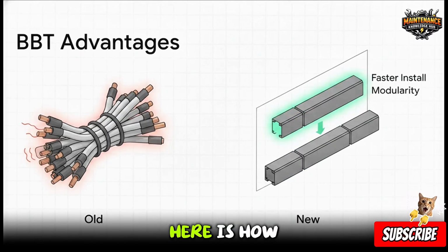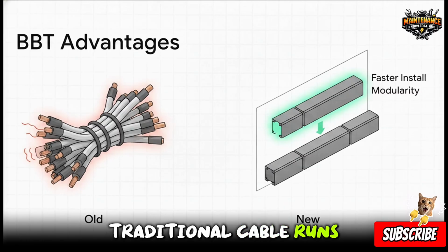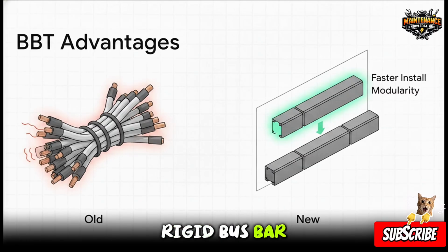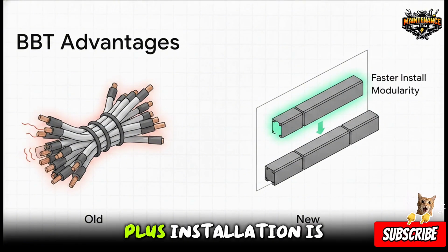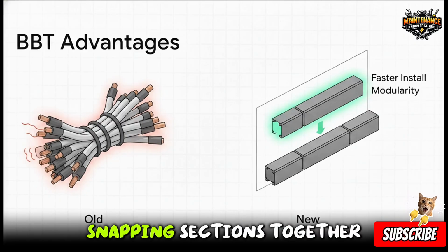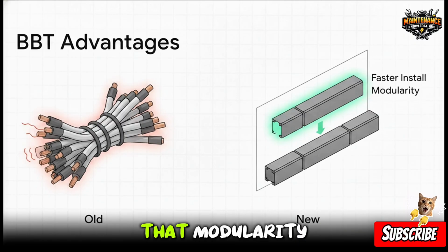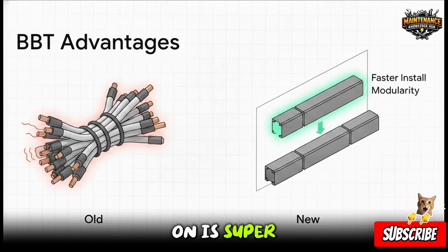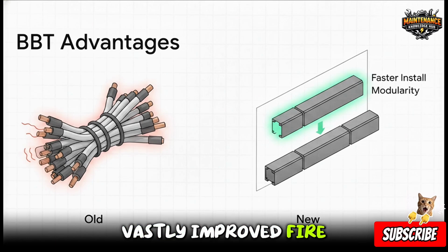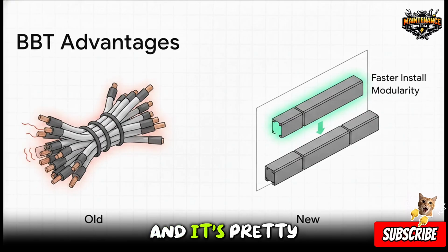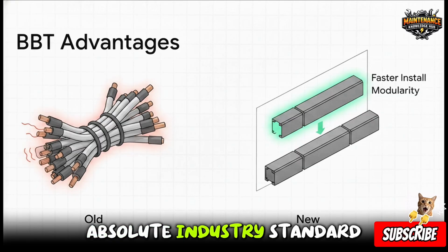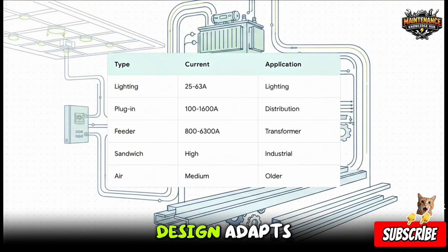What's truly fascinating here is how this system makes long, traditional cable runs completely obsolete. Because of that rigid busbar design, we're talking about a significantly lower voltage drop and much, much better heat dissipation. It boasts a massive current carrying capacity packed into a surprisingly compact footprint. Plus, installation is a breeze. It's modular, so you're basically snapping sections together like giant building blocks. That modularity also means expanding the system later on is super easy. Add in reduced maintenance, vastly improved fire safety, and overall higher reliability, and it's pretty clear why BBT is the absolute industry standard.